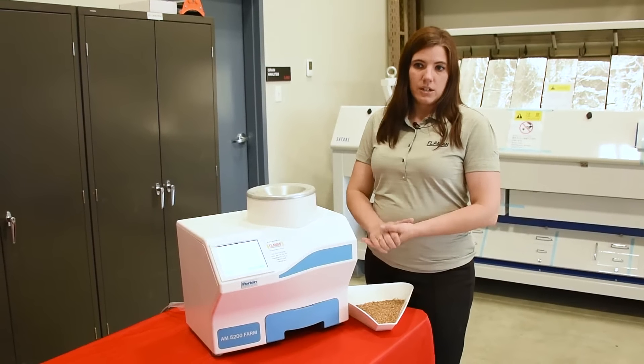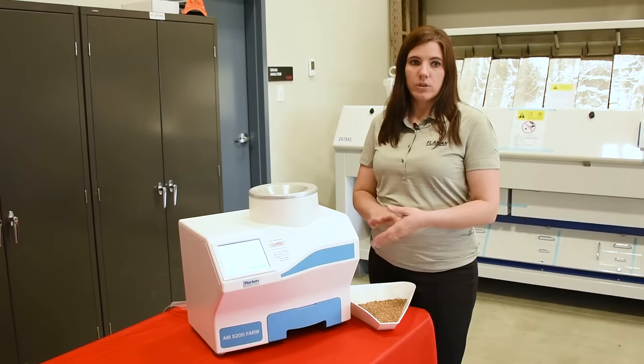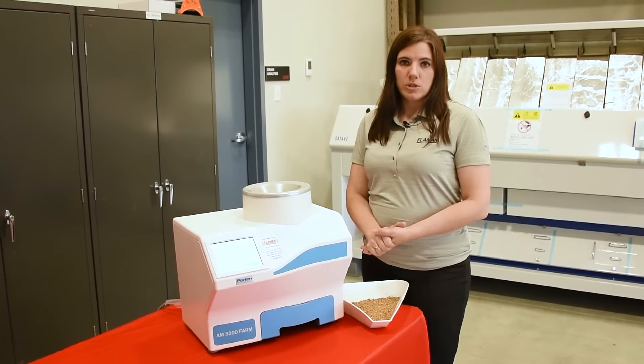This technology avoids the rebound effect with older moisture meters, which is usually a problem for the grain needing to reach a certain temperature. But this meter can test both high and low temperature grains.